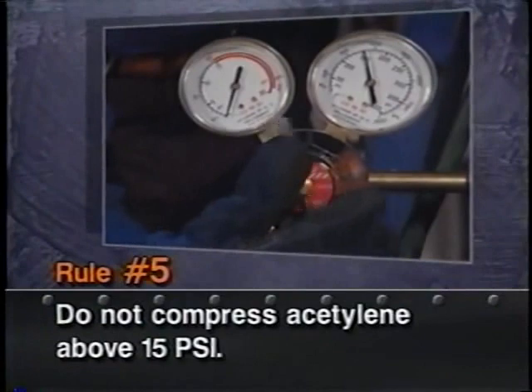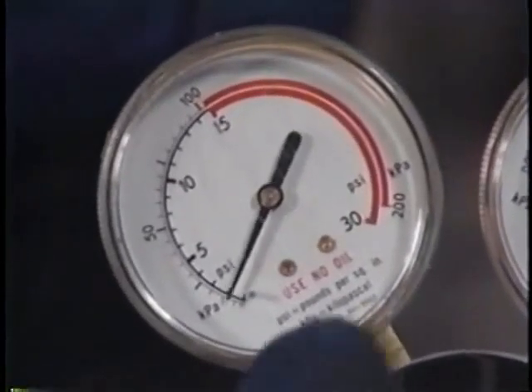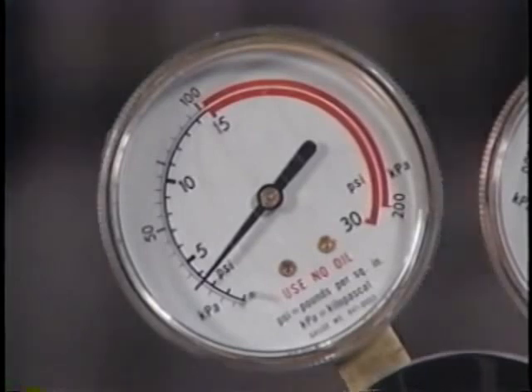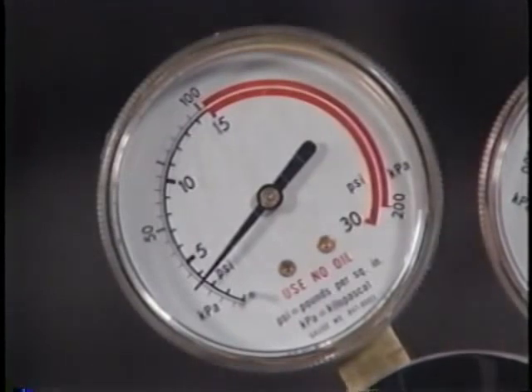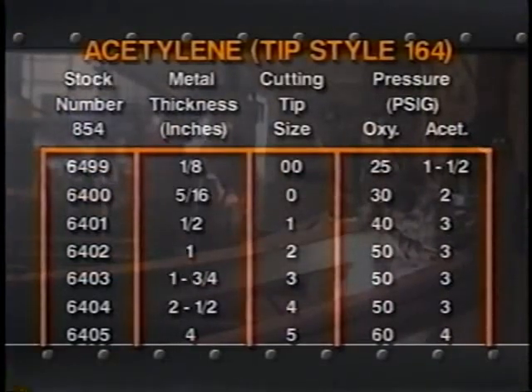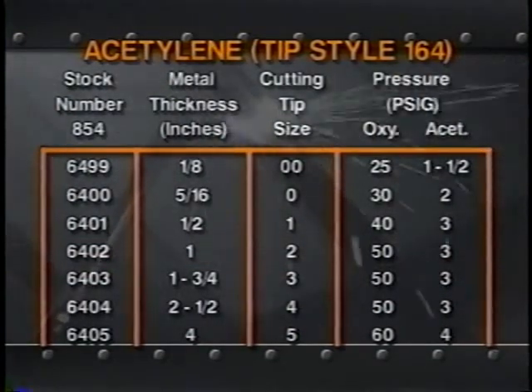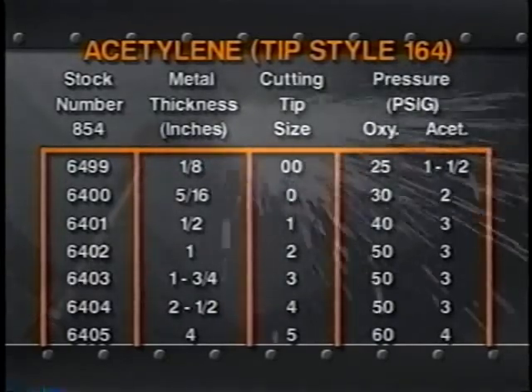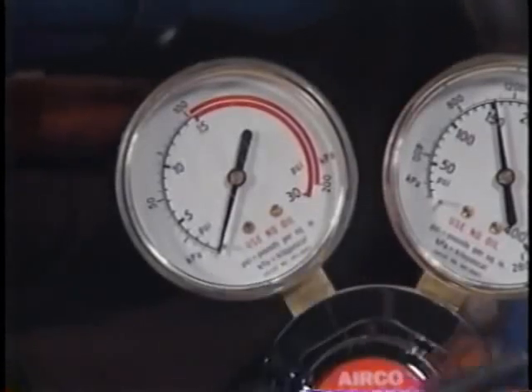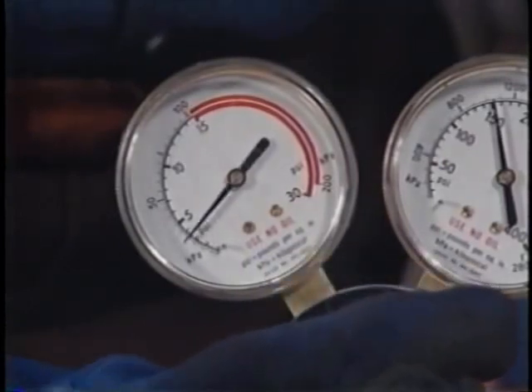Rule number five: do not use compressed acetylene in a free state at pressures higher than 15 pounds per square inch. Acetylene is a man-made gas and it's very unstable. According to chemists, acetylene can be handled safely in the pressure range of 0 to 15 PSI with normal precautions; however, above 15 PSI, acetylene is likely to explode by itself. Seven pounds per square inch of acetylene pressure is all that is needed to cut 14-inch steel, and it is a rare situation which requires more than 10 PSI. Operating up in the 15 PSI range for normal work wastes gas and may put you in a dangerous situation.